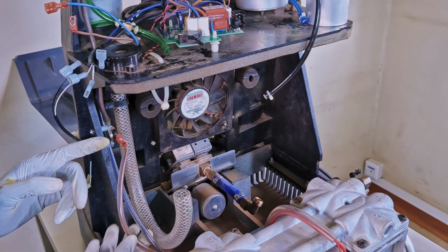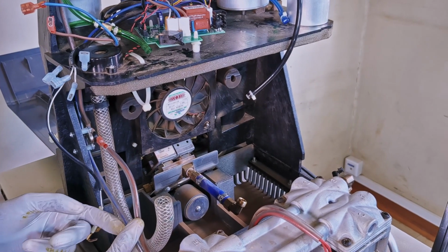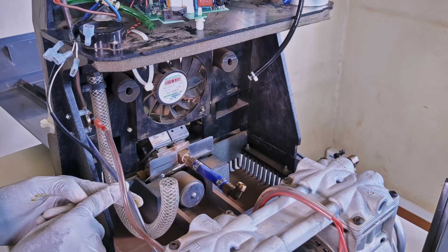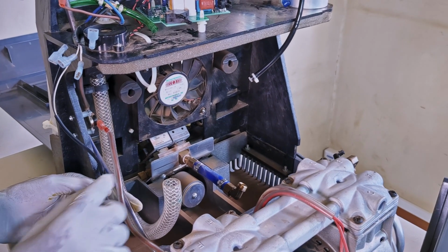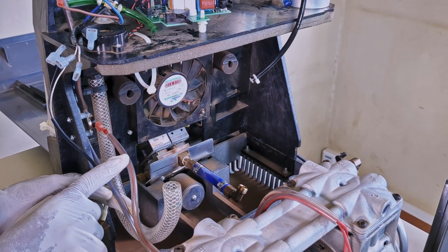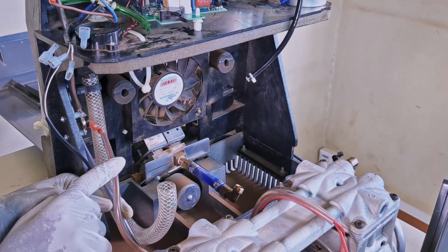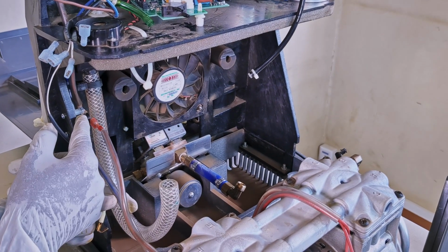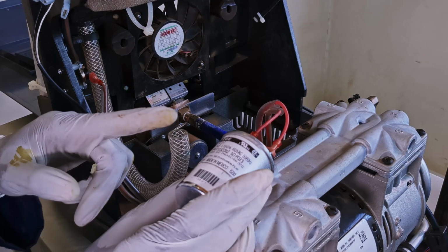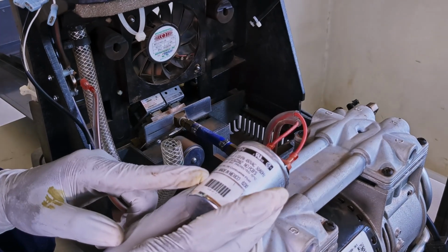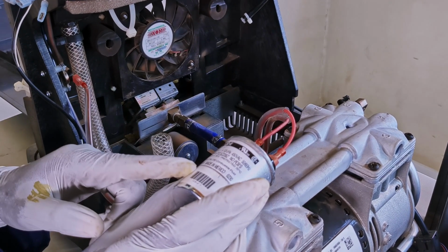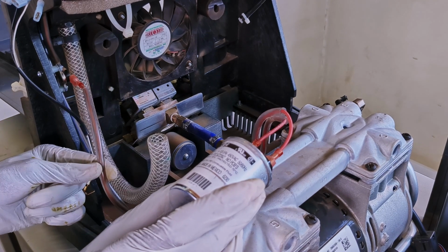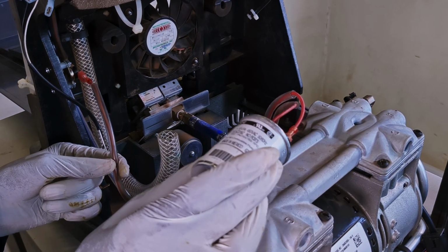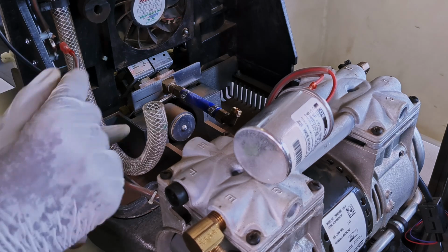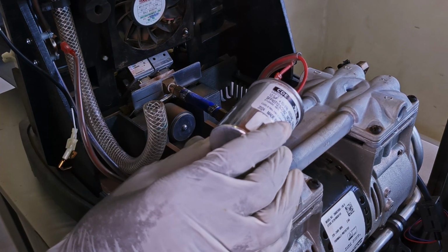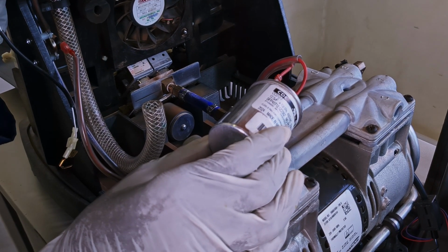As mentioned earlier, these 2 cables are used to power the compressor. The blue one is the neutral cable and the brown one is the live cable. So the live cable is connected in series with the thermal switch. Over here we have the capacitor. This capacitor is also connected in parallel with the live cable. So it also receives 230 volts AC. And that concludes the electrical system of this oxygen concentrator.